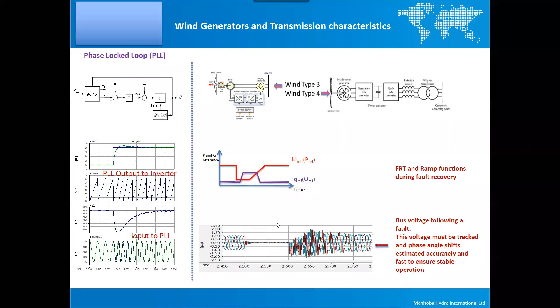Just for your information, you may have heard about fault ride-through requirements and power ramp rate requirements in grid codes, right? When you have power curtailment, reactive power, dynamic reactive support requirements that are mandated in grid codes, all these requirements are achieved by embedding the relevant math into the control systems. So that's why these control systems are so critical, and they have to be properly designed.